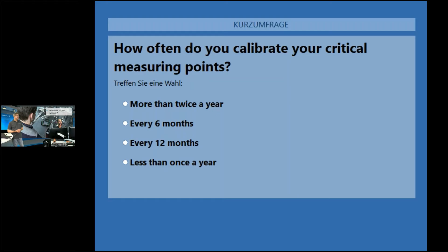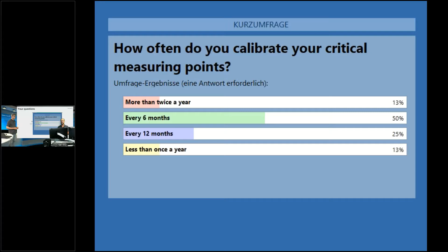You can do. Looks good. So let's see how that looks for you. 50% every 6 months, 13% even more than that, and the rest 12 months or less. All right. That's different because traditionally or folkloristically, once a year is quite often, but really every 6 months is quite popular in the life sciences industry. If you think, I've visited some plants. For example, I was once in a plant that had 1,000 thermometers in their process, which were calibrated once a year using a 10-point calibration because it's written in their SOP. Imagine how much time is spent to do this.